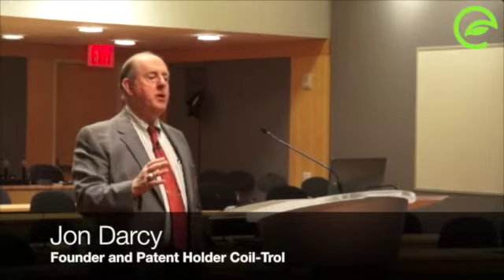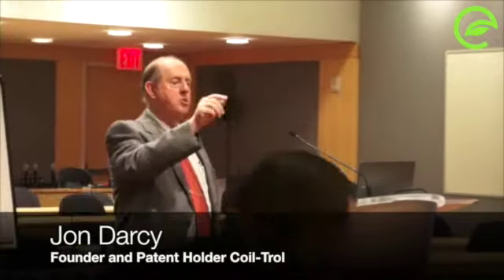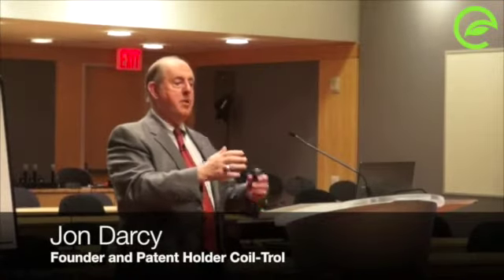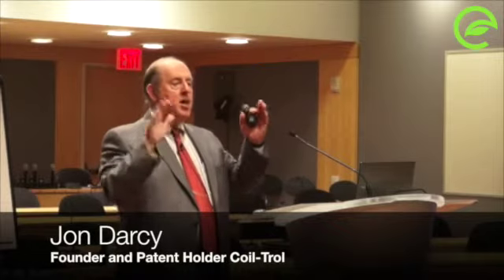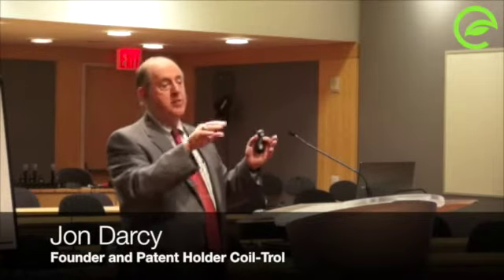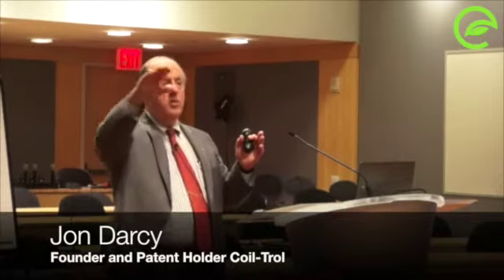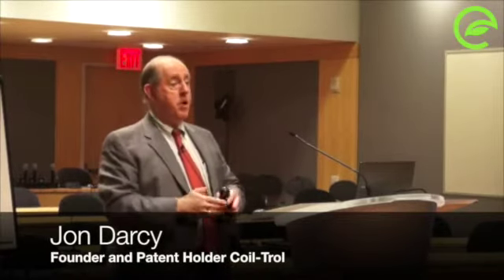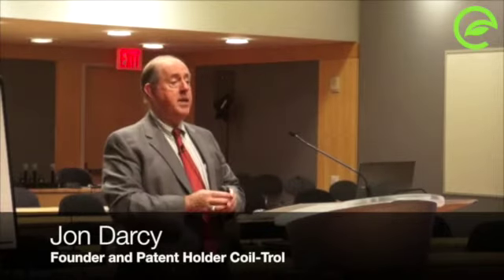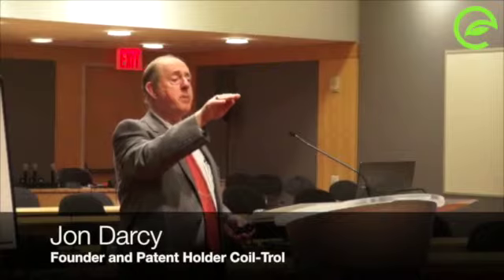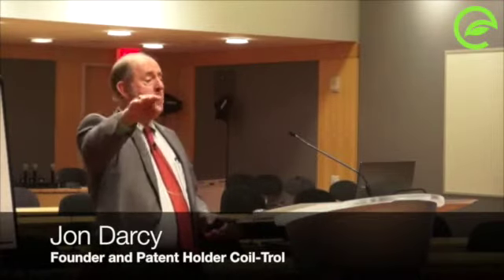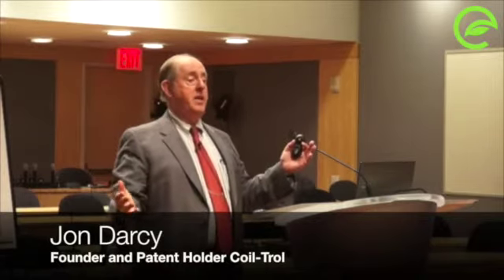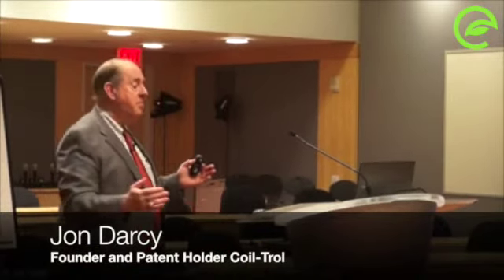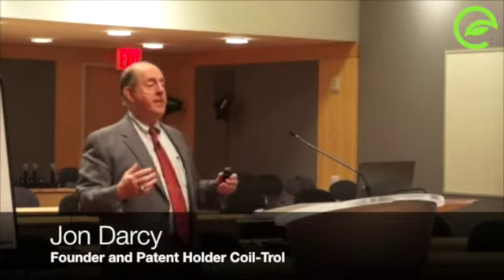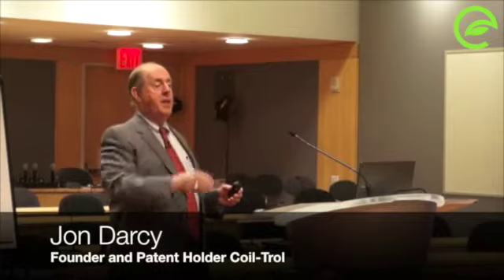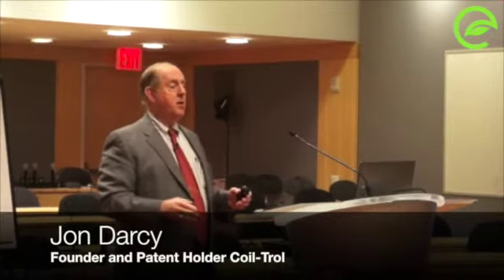Well, it wound up when the load dropped off and the valve started to close, the discharge temperature would go down, but the valve didn't necessarily close all the way. So you didn't see the problem, and plus pneumatics are a lot slower than electronics. So you wind up not seeing that problem with laminar flow so much in pneumatics. But when you have a PI controller, that valve could be 10% open at 5% of load. It could be 10% open at 100% of load. It could be anywhere in between. So the problem is something that we created for ourselves when we put DDC control in, and we decided that we wanted to get rid of that proportional offset and make that air handling unit much more efficient.